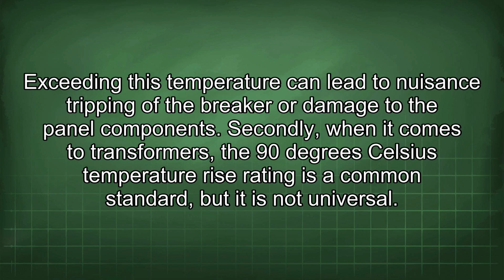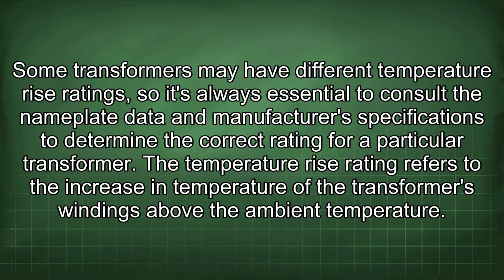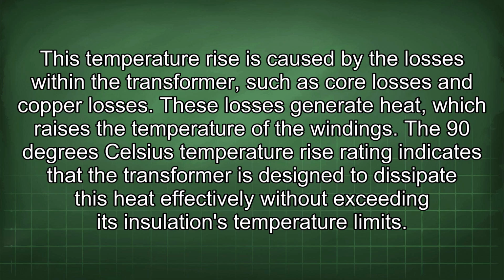Secondly, when it comes to transformers, the 90 degrees Celsius temperature rise rating is a common standard, but it is not universal. Some transformers may have different temperature rise ratings, so it's always essential to consult the nameplate data and manufacturer's specifications to determine the correct rating for a particular transformer. The temperature rise rating refers to the increase in temperature of the transformer's windings above the ambient temperature. This temperature rise is caused by the losses within the transformer, such as core losses and copper losses. These losses generate heat, which raises the temperature of the windings. The 90 degrees Celsius temperature rise rating indicates that the transformer is designed to dissipate this heat effectively without exceeding its insulation's temperature limits.